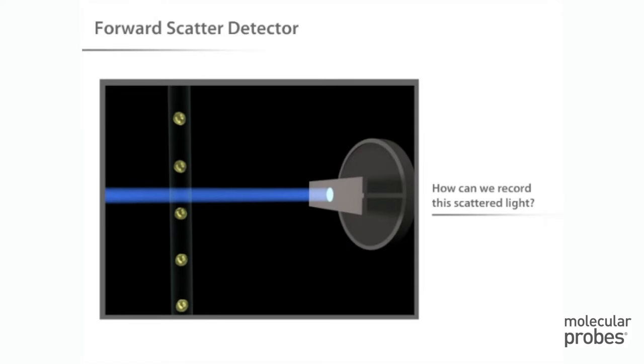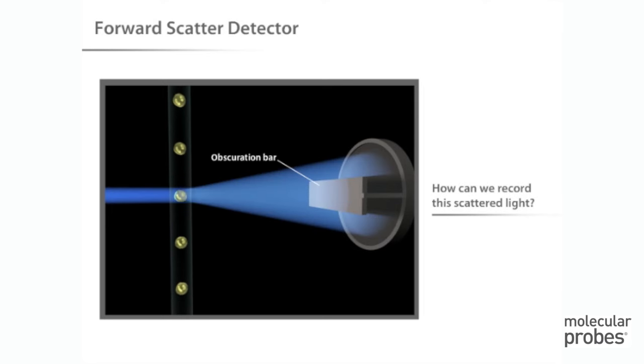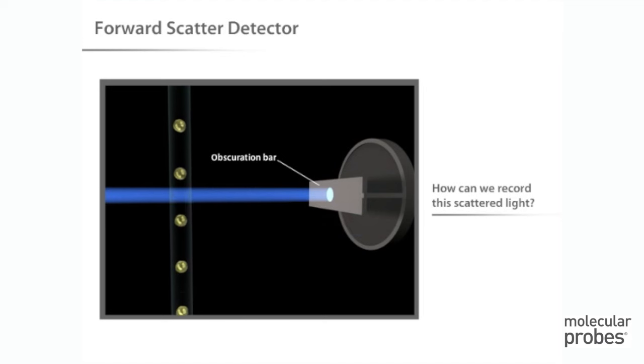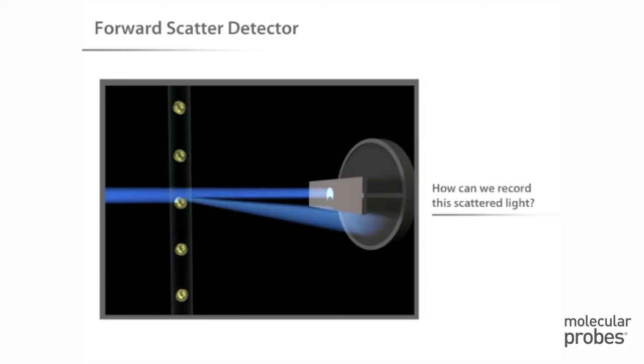But how can we record this scattered light? Light is quantified by a detector that converts intensity into voltage. In most cytometers, a blocking bar, called an obscuration bar, is placed in front of the forward scatter detector. The obscuration bar prevents any of the intense laser light from reaching the detector. As a cell crosses the laser, light is scattered around the obscuration bar and is collected by the detector.